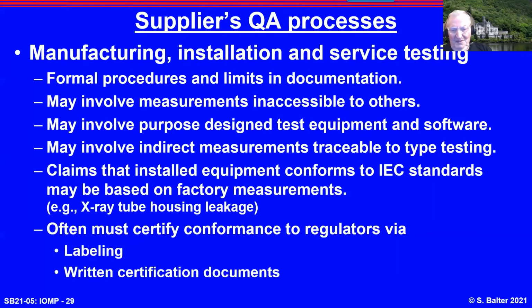They will claim that installed equipment conforms to IEC standards based on the measurements. One of the best examples of this is X-ray tube housing leakage, where the manufacturers essentially will test each housing before shipment in a 4-pi geometry, something that just can't be done in the field. The conformance is certified to the regulators and perhaps to the medical physics community with the labeling and written certification documents. One of the things being discussed in IEC is to make the individual serialized documents more readily available to the end institution.